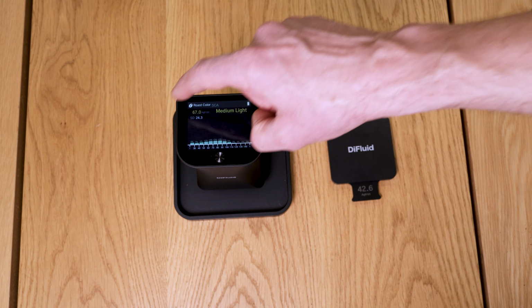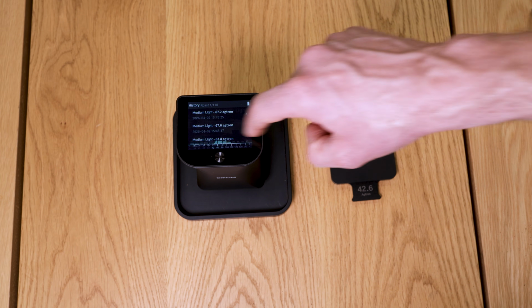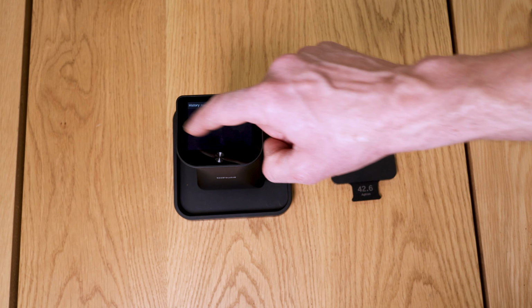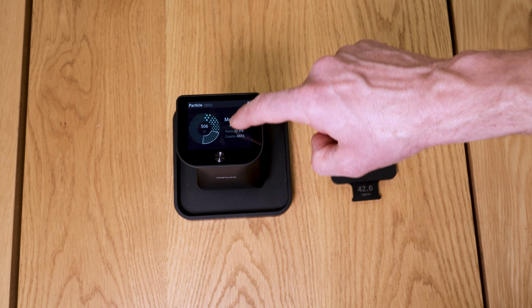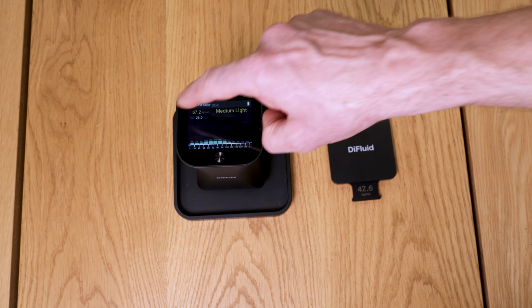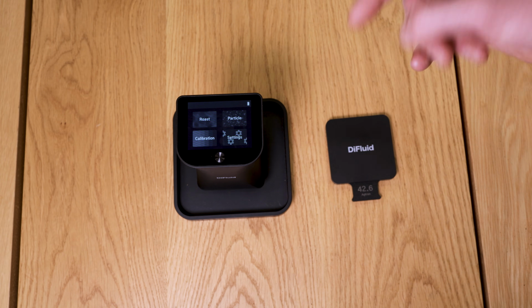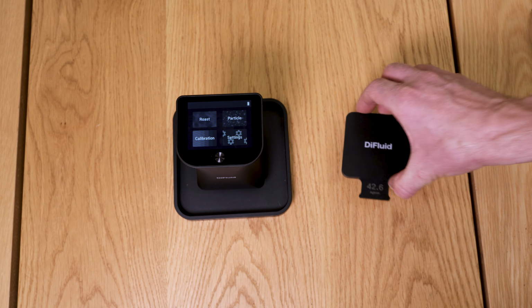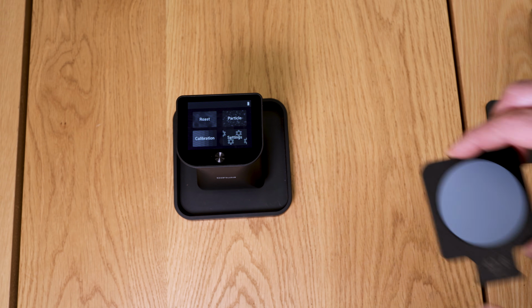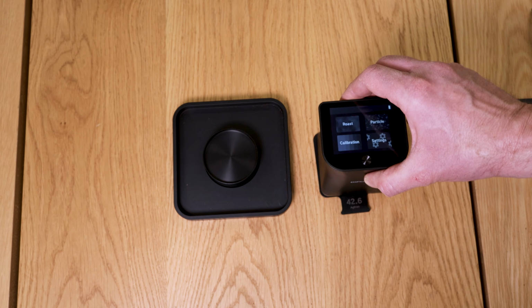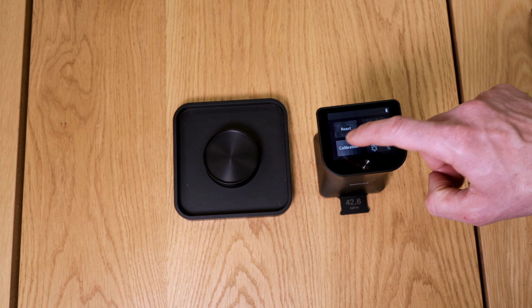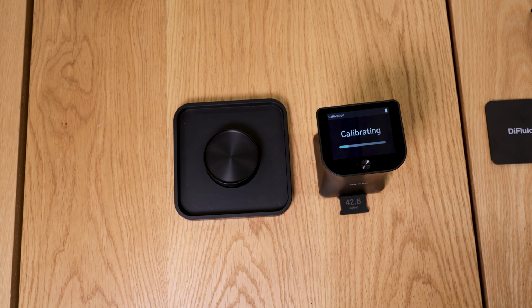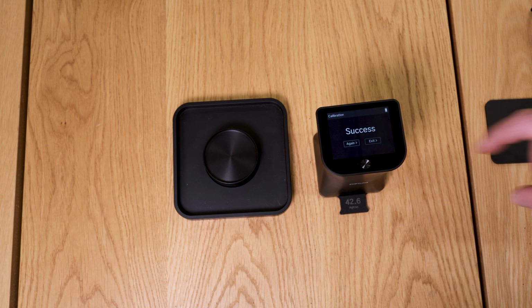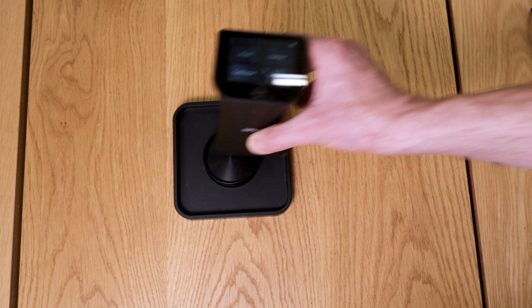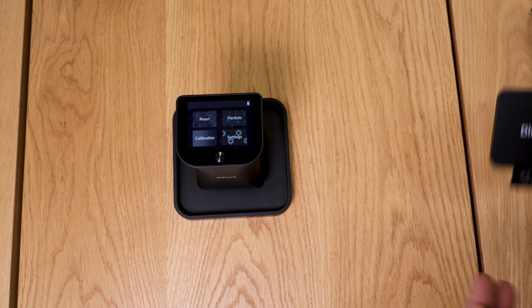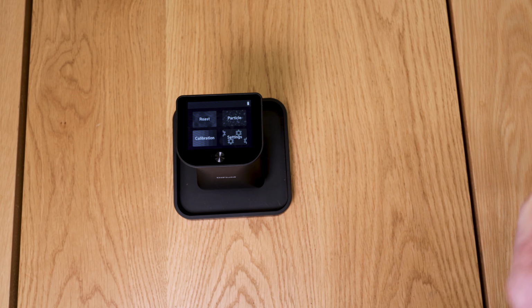Can go back, can do the same then for, okay, let me check. So I can go back, but then I can do the same for the particle measurements, where I see the previous particle measurements. And now we are going to do, as with all the other devices, a calibration. So I'm putting the tool on the little calibration plate, press on calibration, start. It's calibrating. Close this again and put it back in the little bag.